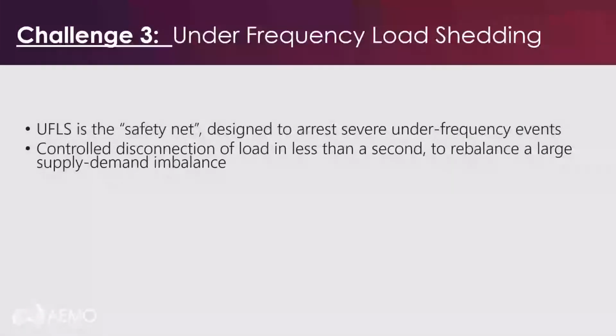Challenge 3 then, and the last one I'll speak to today, is around our under-frequency load shedding schemes. Under-frequency load shedding is the safety net we use to arrest a very severe under-frequency event, when we have a trip of multiple generating units, for example. It relies on the controlled disconnection of loads in less than a second, usually around 200 to 300 milliseconds, for those relays to respond and very quickly rebalance a large supply-demand imbalance. So it's an automated shedding of load to correct a very severe frequency disturbance.